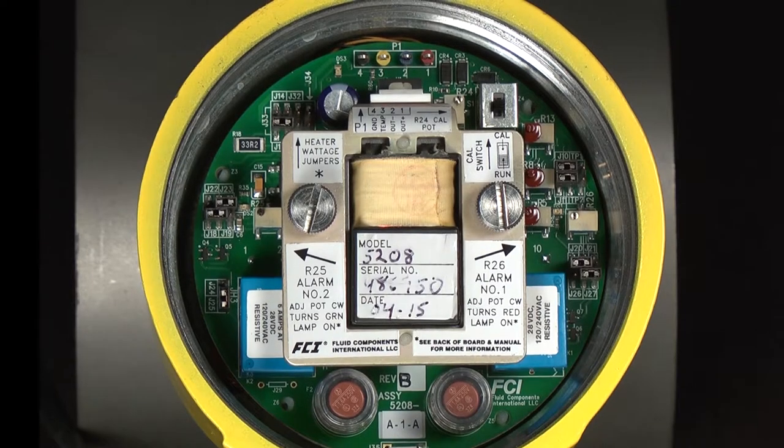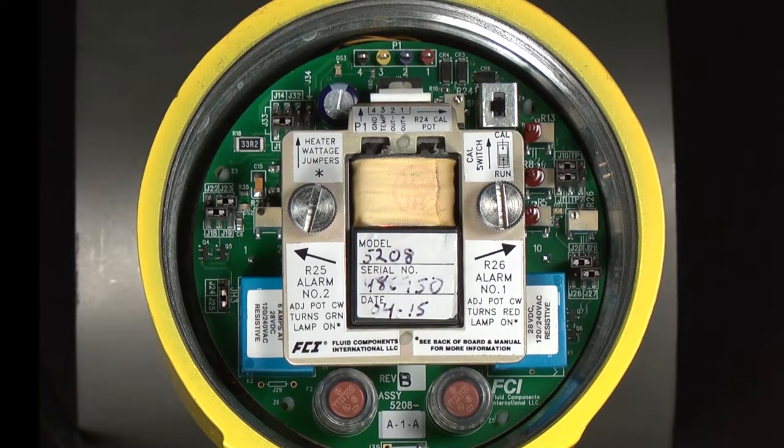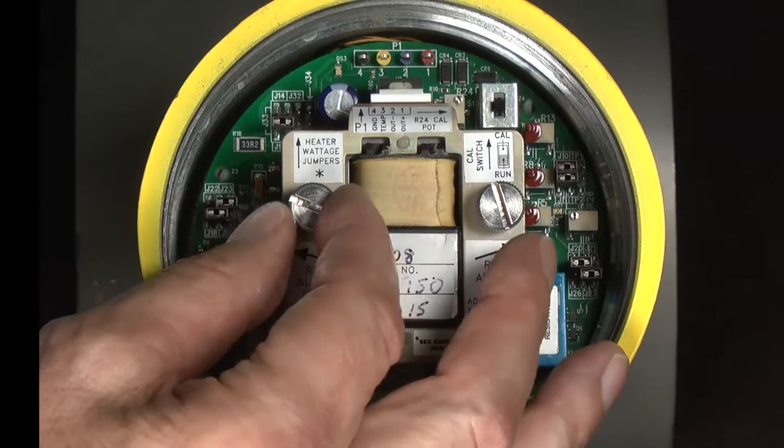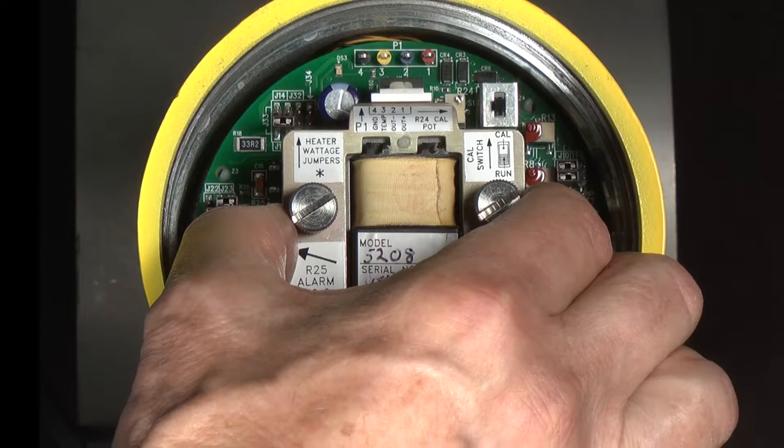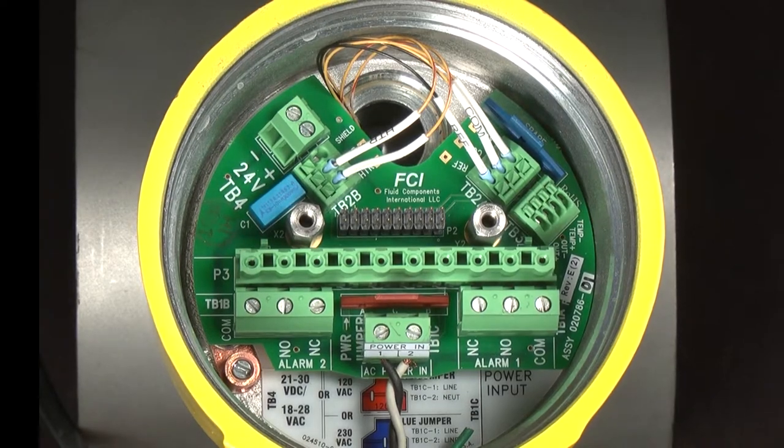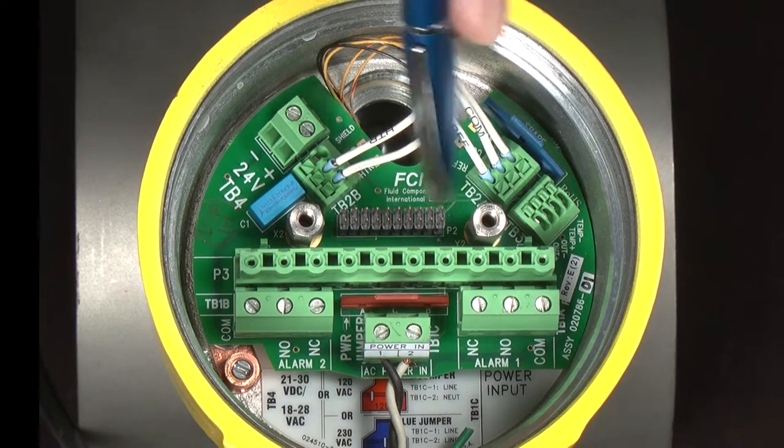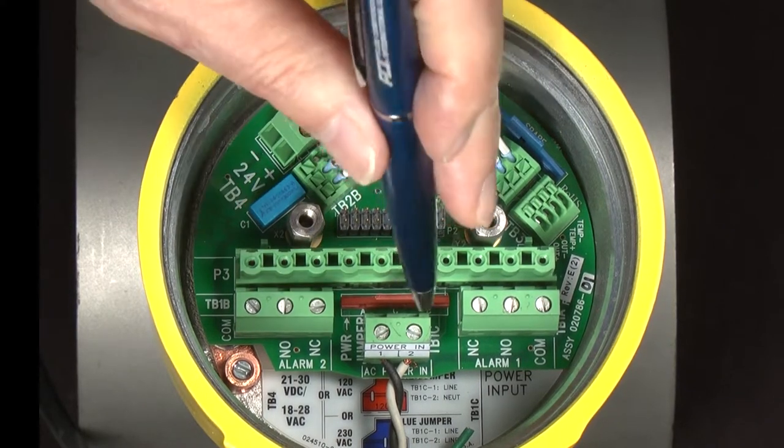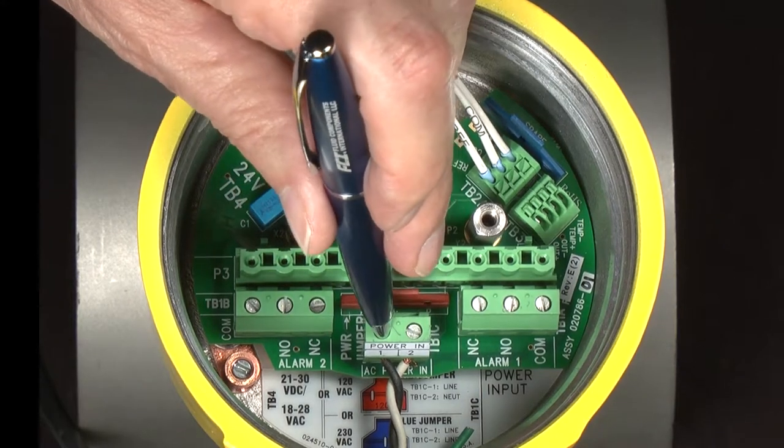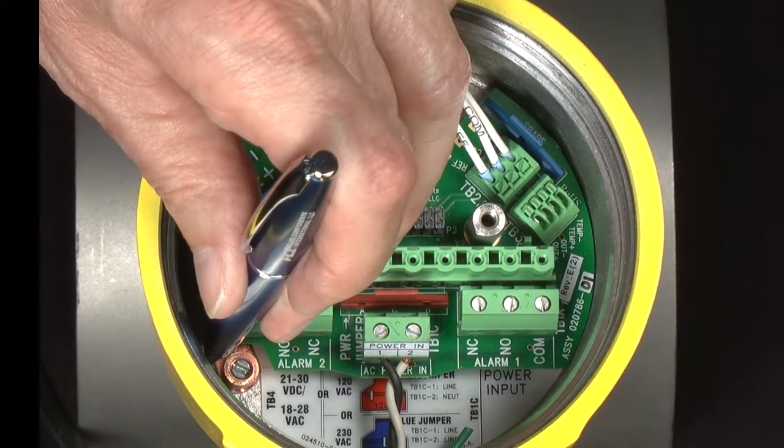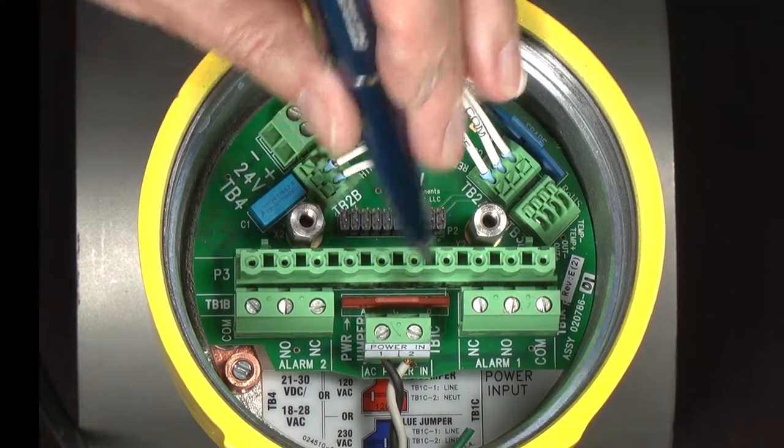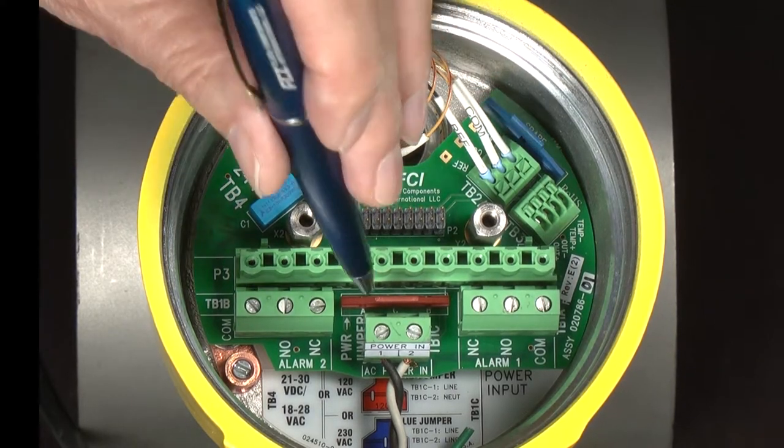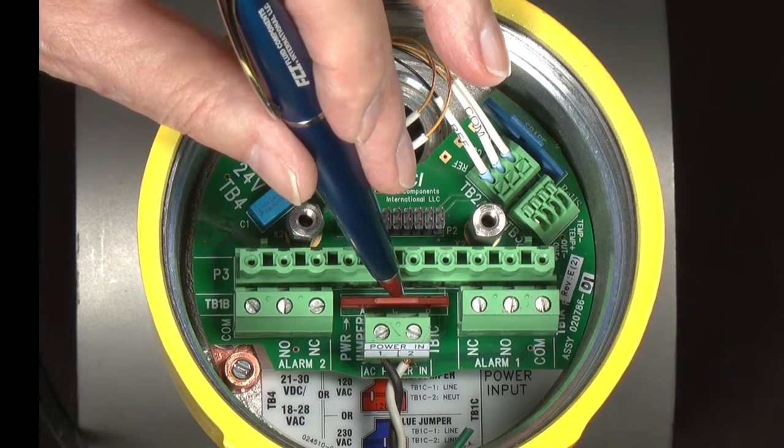Now let's take a closer look at the 5208 circuit board. The 5208 circuit board has a top and bottom board. The top board is connected to the bottom board by these two screws; you loosen them up, and you grab the top board by the transformer, pull it straight out. Make sure the power is off first. The bottom board is connected to the enclosure by these two hex nuts. You connect your power to the TB1C connection here, and your ground to this lug that's attached to the enclosure over here. There are two jumpers, a red jumper and a blue jumper. The red jumper is for 120 volt AC, the blue jumper is for 230 volt AC.